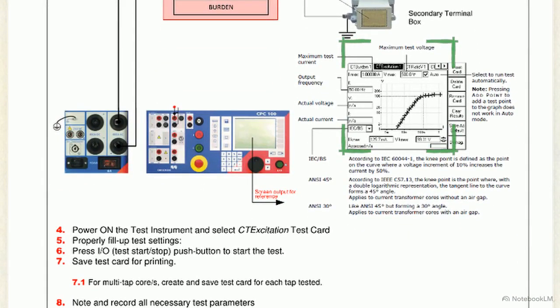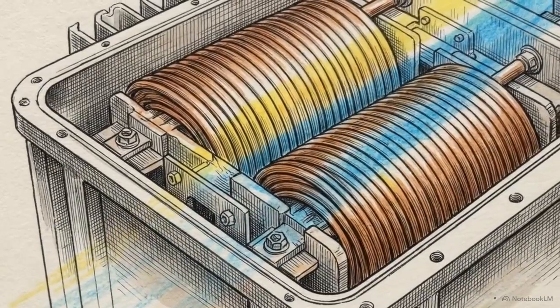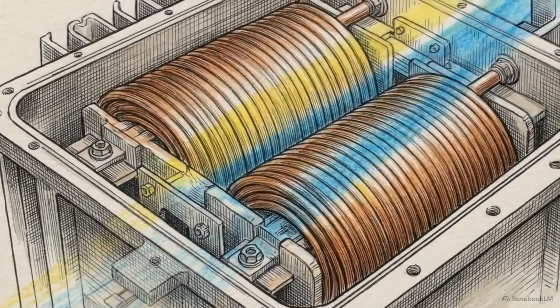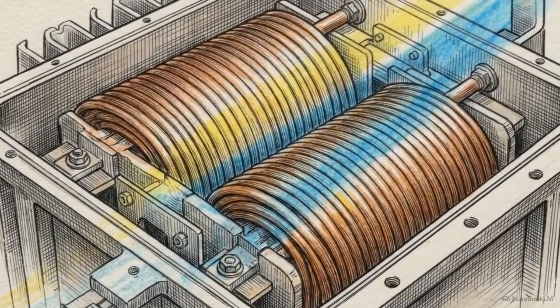Following the IEC 60044-1 standard, the system identifies the exact knee point on the logarithmic curve, the specific coordinate where a 10% increase in applied voltage results in a 50% spike in exciting current. Alternatively, the IEEE standard defines saturation differently, pinpointing the exact spot where the tangent line to the curve forms a 45-degree angle. After determining saturation, we measure the winding resistance to evaluate the physical integrity of the secondary copper coils.